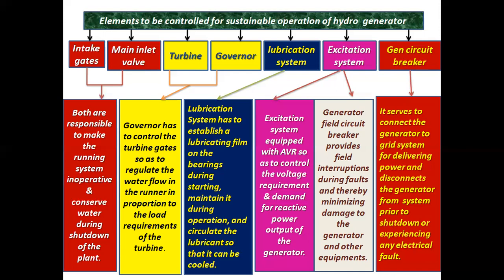Excitation system. Number one, the excitation system is equipped with an AVR, that is, automatic voltage regulator, so as to control the voltage requirement and demand for reactive power output of the generator. Number two, the generator field circuit breaker provides field interruption during faults, thereby minimizing damage to the generator and other equipment. Last one is the generator circuit breaker, which serves to connect the generator to the grid system for delivering power and disconnects the generator from the system prior to shutdown or on experiencing any electrical fault.